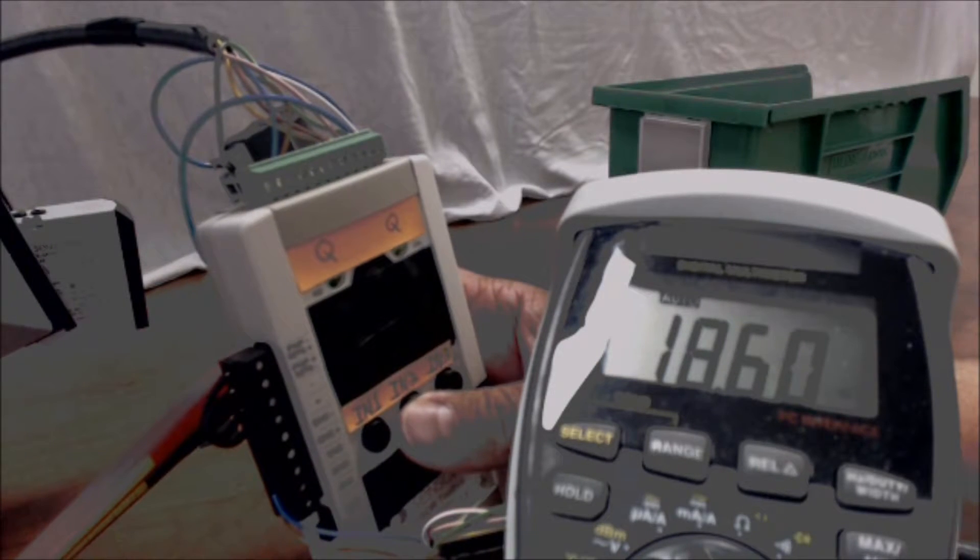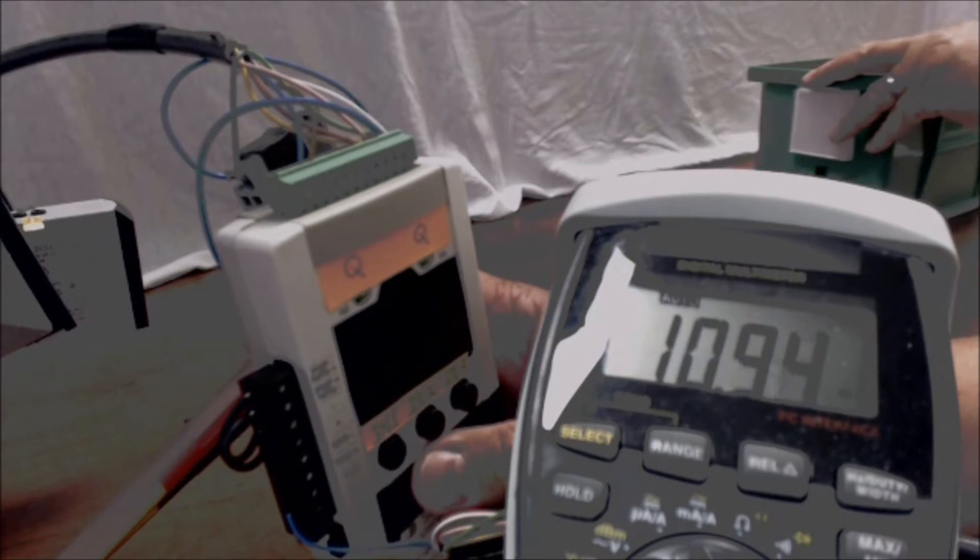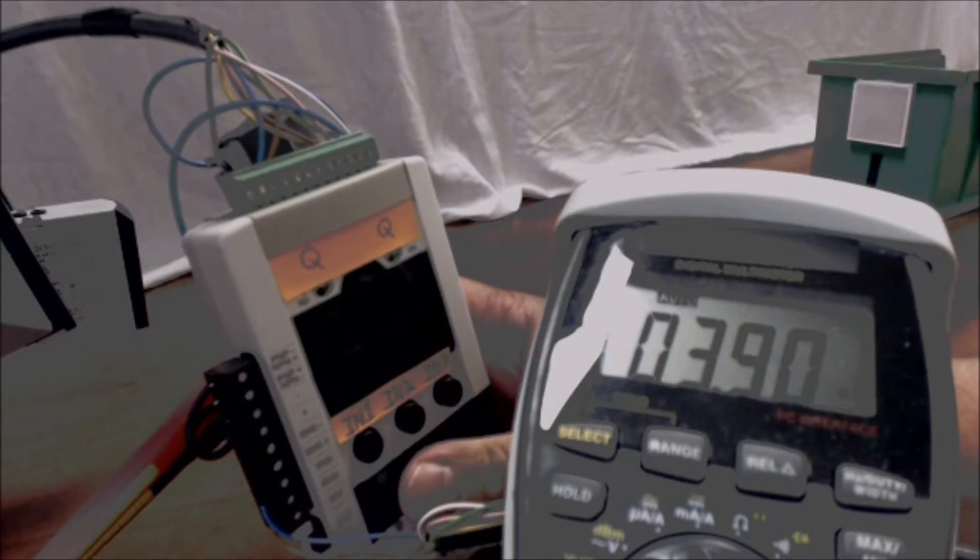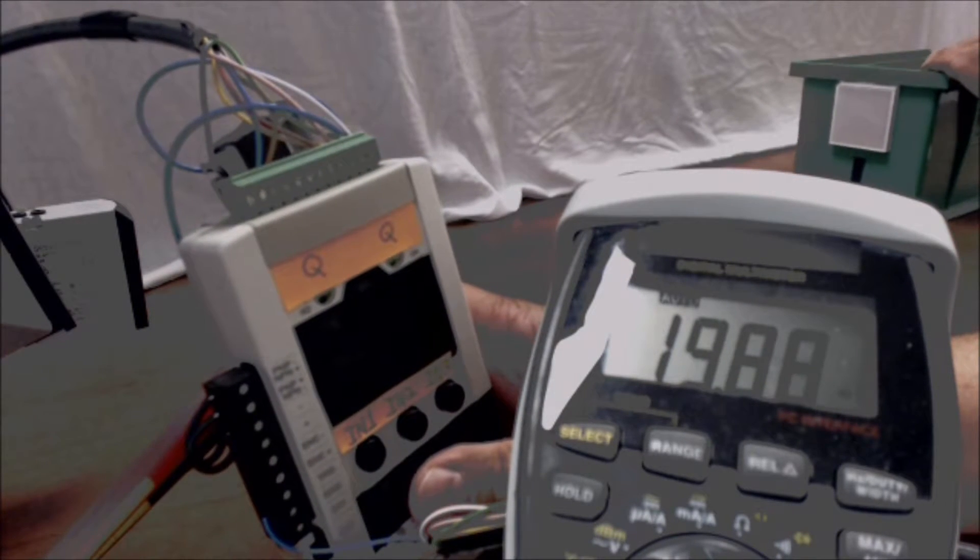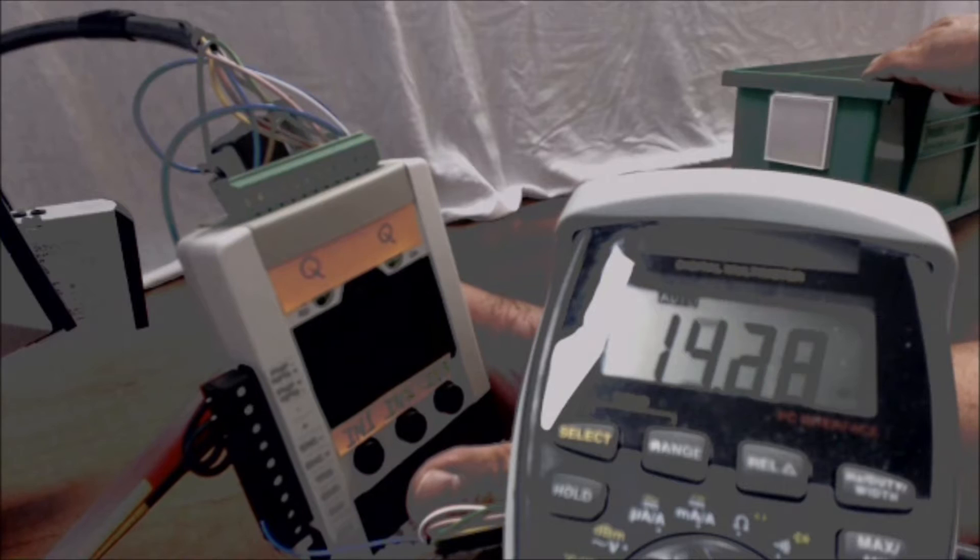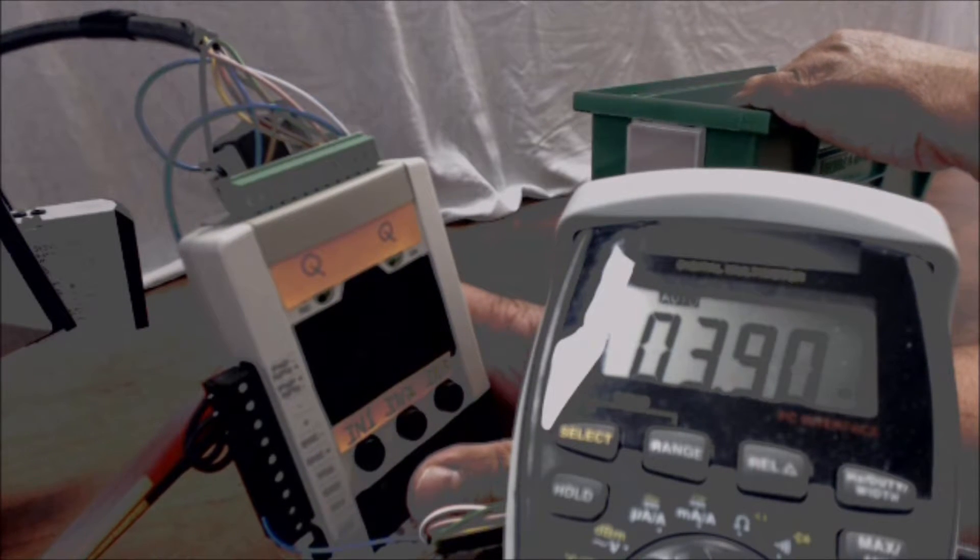Here we have the target in place. We press and hold for more than three seconds until the lights flash on the sensor. Then, we move the target to the second position and tap the button. You see it went from 4 milliamps to 20 milliamps. Now the sensor's taught. At 20, we bring it forward to the other taught position, and it goes down to 4 milliamps.